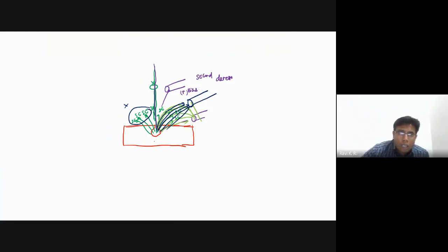But another reason we don't go closer is that this can destabilize the incident beam as well as the backscatter electron. Let's say you go closer here and put a positive bias. The backscatter electron comes a little bit later and should come like this. So if you put it closer to the incident electron, this can pull the backscatter electron also. That can damage the secondary electron detector.